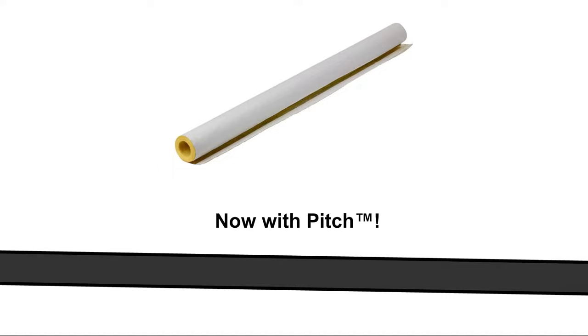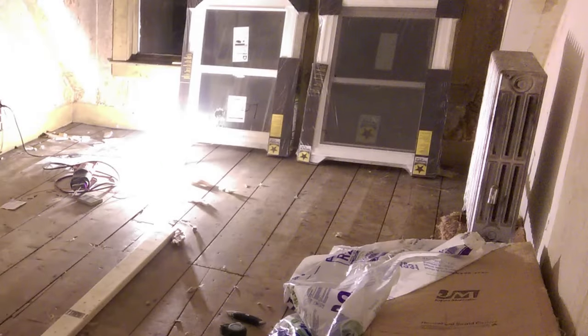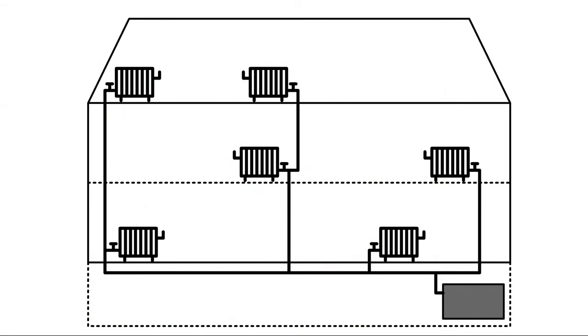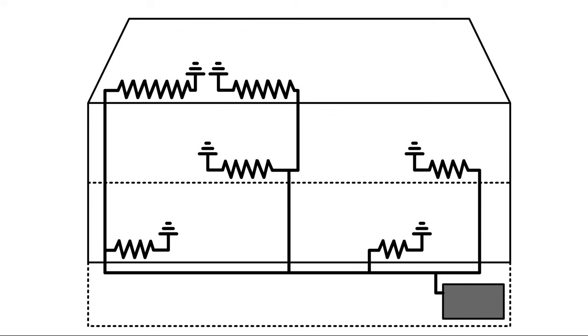This gave the radiator some heat, but not enough, and this is where the wonders of balancing the radiator system comes in, using appropriately sized steam vents. The steam radiator system behaves much like a circuit, and like electricity, steam tries to find the path of least resistance. Which means that steam favors radiators which allow air to escape the easiest, and also the radiators closest to the boiler. This poses a problem, especially for radiators very far from the boiler, such as radiators located on upper floors.